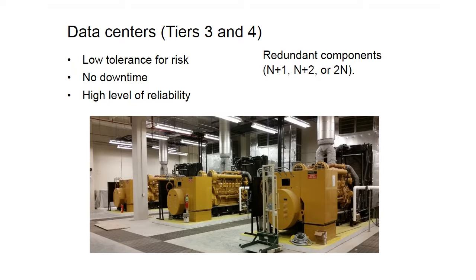They have a low tolerance for risk. There's not a lot of downtime, or no downtime, high level of reliability. So a lot of times with the data center, you'll see redundant components within the standby power system. So you'll see N+1 generators, N+2, maybe even a full 2N system. These usually fall into a tier 3, tier 4, what they call tier 3 plus in some sources, where you want to meet the requirements of tier 3, but the expense to get to a complete tier 4 is too high, so they'll try to take specific components and make sure they're fully redundant, and then others they'll try to just do an N+1 or N+2.